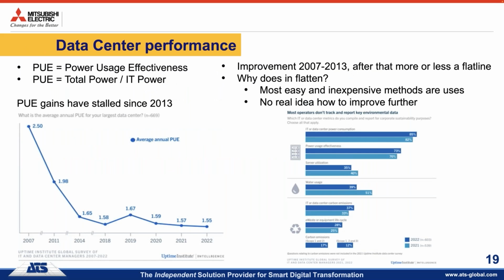So the PUE, Power Usage Effectiveness, tells you something about data center efficiency. This is a table coming from the Uptime Institute, and if you look at the left part, in 2007 the general average worldwide PUE was 2.5. That means that at that moment, even more power was going to infrastructure than to IT. Then they started to improve, and by 2013 it was 1.65. What we see since then is that it has more or less flatlined. The last report, which came out about a month ago, shows the worldwide PUE is 1.55 - you see that it hasn't improved anymore. The reason is that the biggest impact on improving was just cold or hot air containment, and after that, most data centers had no good idea how to improve anymore, beside buying slightly more efficient equipment.